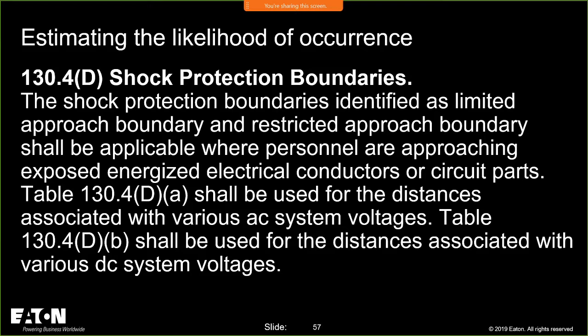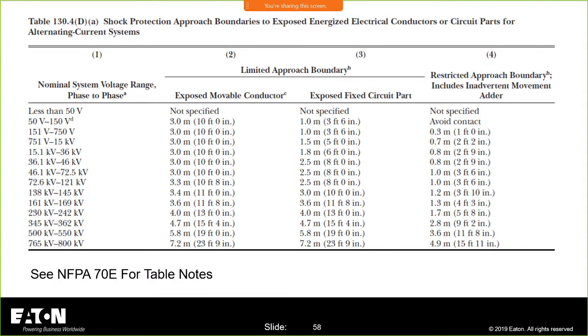Now, the shock protection boundaries are established in 130.4(D), and the table in 70E is, I think, an even better example to help us understand what those boundaries are. We have a limited approach boundary and we have a restricted approach boundary. There's our less than 50 volts, and then 50 to 150. That's typically more than likely going to be the area that you work in the most.